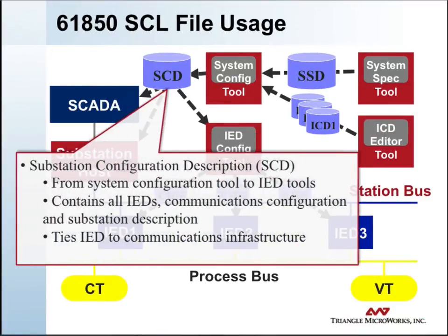The substation configuration description, or SCD file, is basically a combination of those two. It puts together the substation specification and the build-out of all the IEDs, and within a system configuration tool, this generates a full substation configuration description. This basically contains all IEDs, communications configuration, and the substation description. It ties the IEDs into both the communications infrastructure and the power system description.